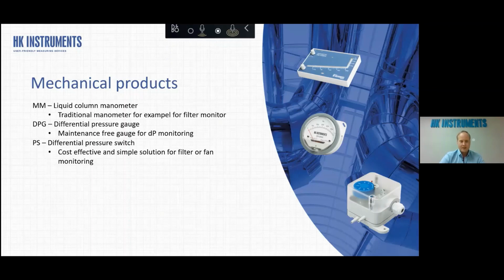And then we have this gauge, DPG, which is also very convenient because it's basically maintenance free and a good visual differential pressure gauge for many different applications. You can use it for air handling unit to see the filter pressure, or you can use it to monitor the differential pressure between different rooms. For example, in the clean rooms, because you can clearly see the needle from far away, so it's then a good visual check for many different applications.